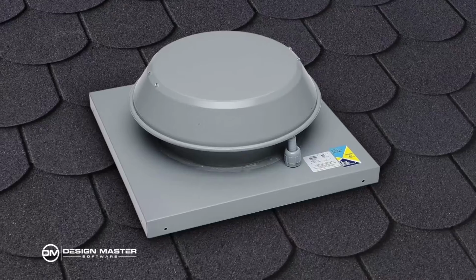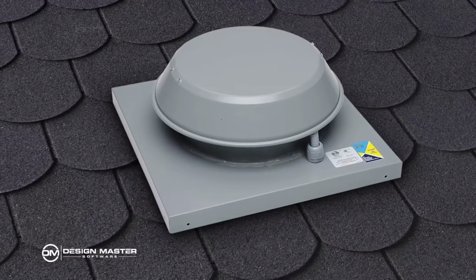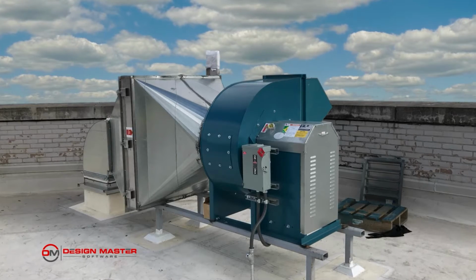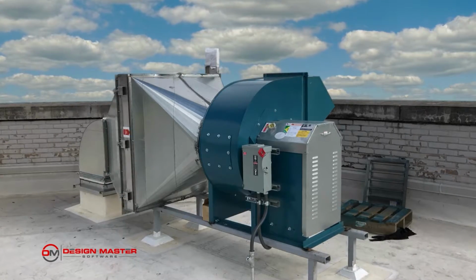Is there any way to minimize the load of the subducts so that the backup unit can be as economical as possible? Yeah, not all fans are created equal. And here is where mechanical engineers and contractors can sometimes get lazy and give you a very inefficient fan that causes you to increase the size of your backup systems. The typical subduct fan up on the roof is a mushroom fan, and they're horribly inefficient. They're easy to install and inexpensive, but they are inefficient. And since they run continuously, one might argue that that's an issue as well from an energy efficiency standpoint. The other type of fan is just a simple utility fan, and they can be made much more efficient and also reduce the power consumption you need.